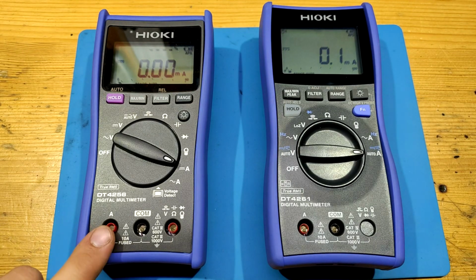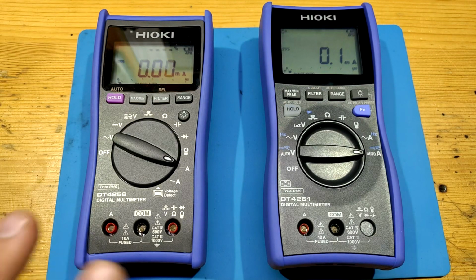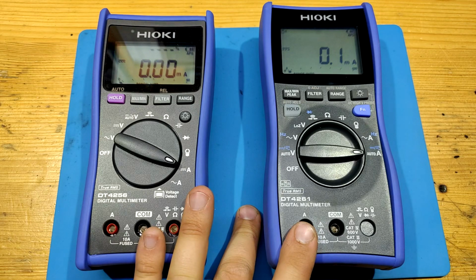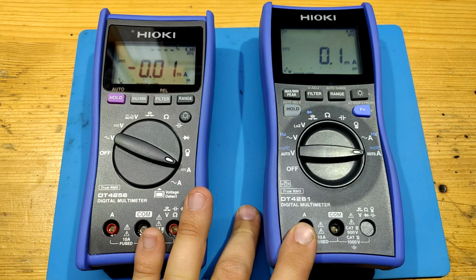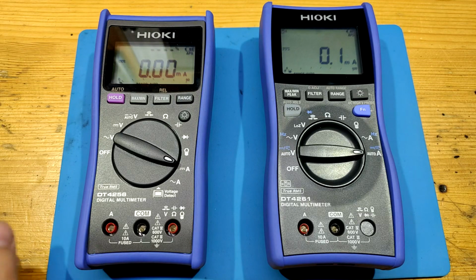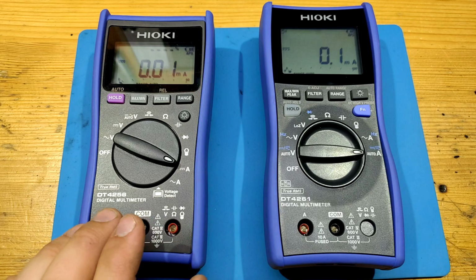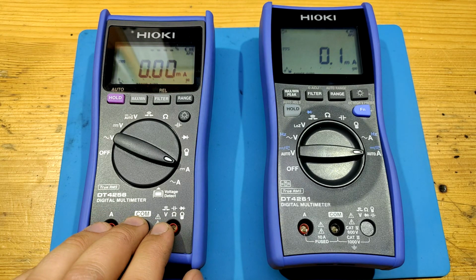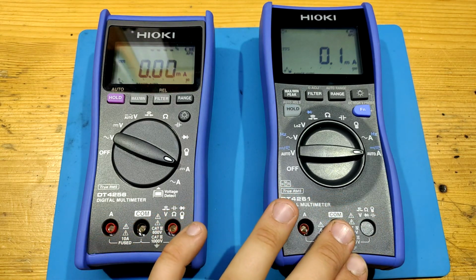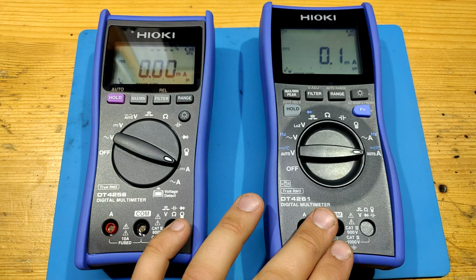My sample of 4256 is a little off calibration, I would say, as it had approximately minus 0.3 milliamp offset when there was no passing current, and I didn't know why. Both these meters are samples for demonstration purposes where people go around and play with them, so it may be caused by this. I measured error for 1 milliamp, and 4256 had an error of 0.108% from range. 4261 had an error of 0.38% from range.